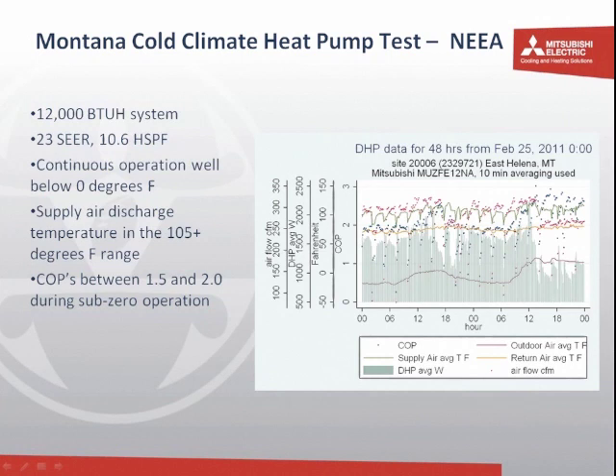This is the 1-ton system. It's rated at 23 SEER, so very high efficiency, and it has continued to operate even when the outdoor ambients are as low as negative 25, which is represented on the Fahrenheit scale here. These are the outdoor temperatures during this particular test. This happened to be the 48 coldest hours in 2011 when this was being tested. The temperatures of interest are the supply air temperature, which continues to be at or around 100 degrees. That's this green line across here.